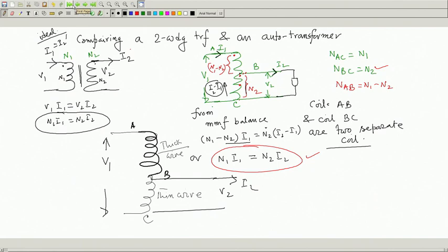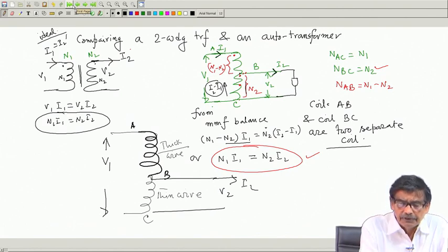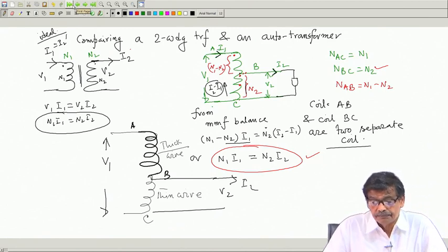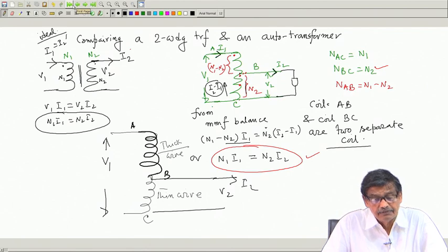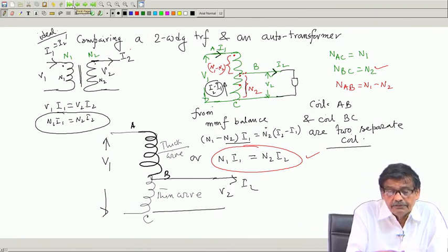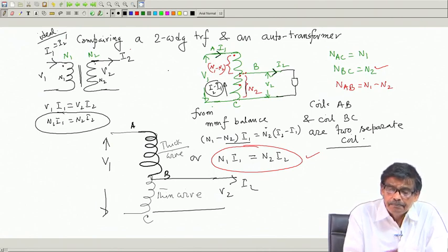Remember in our last class, with the help of an autotransformer, I can change the voltage from one level to some desired level, as we have done with a two winding transformer, and I could transmit a certain amount of kVA. Suppose I want to change the voltage level from V1 to V2, and it will deliver a kVA of V2I2, or the transformer will handle a kVA of V1I1 or V2I2 - they are the same.